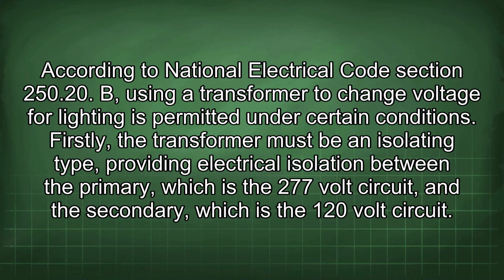According to National Electrical Code Section 250.20(B), using a transformer to change voltage for lighting is permitted under certain conditions. Firstly, the transformer must be an isolating type, providing electrical isolation between the primary, which is the 277-volt circuit, and the secondary, which is the 120-volt circuit.